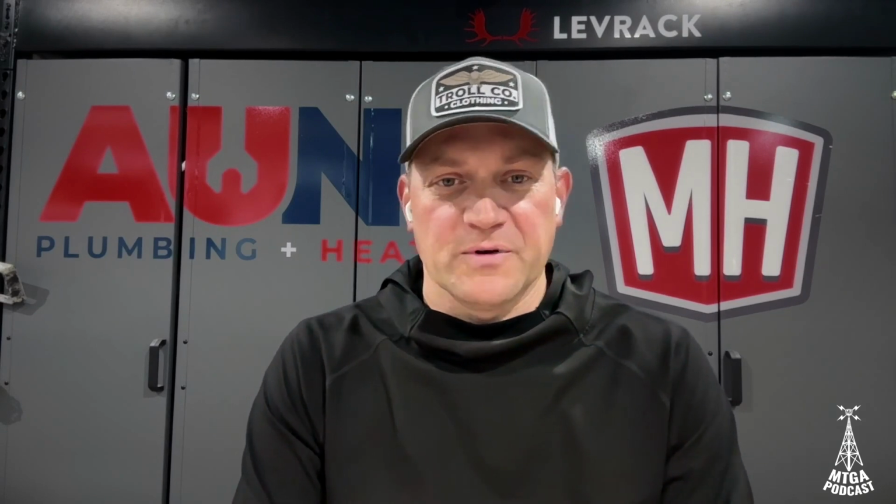So the indoor unit, for imagination purposes, is a little bit smaller than a wall hung tankless water heater. I think that's a great comparison size wise. In this Viessmann case, it's got a single circulating pump built into that indoor unit and a three-way mix or diverting valve that handles our hot water versus space heat. And then that indoor unit is connected to a buffer tank.